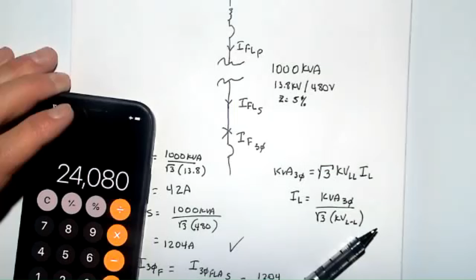But if it's low enough, the calculations work out so that we can ignore the impedance of the upstream transformers and cables and everything else, and just use the nearest upstream transformer as our main source impedance. That becomes especially important when you're doing fault calculations and even harmonic analysis, to be honest with you, for resonance and things like that. So if you can understand transformer impedances and calculate all that, then you can figure out how that comes together. How much of a difference is it? It's usually less than 5%, and in fact, it errs on the conservative side.